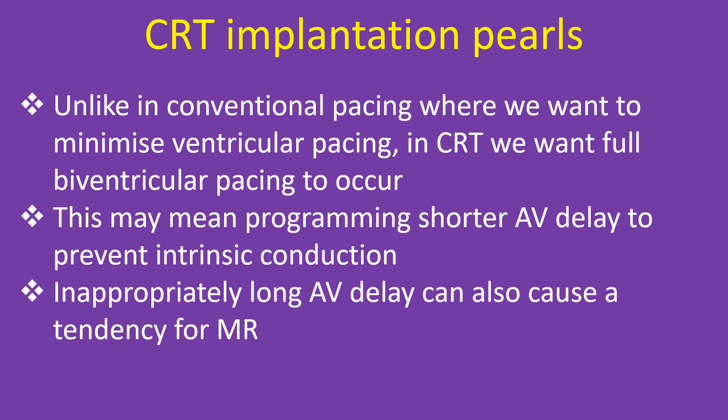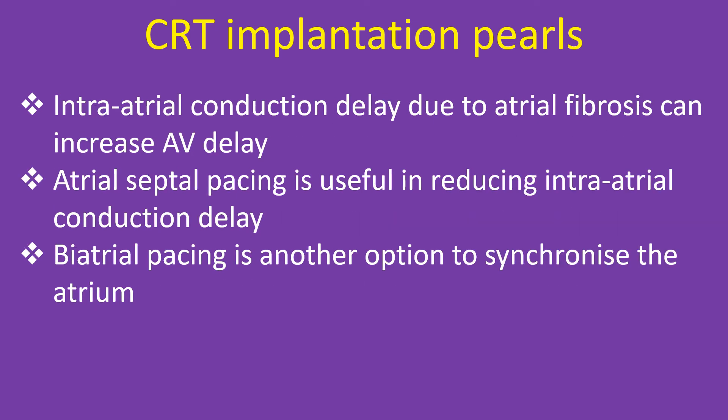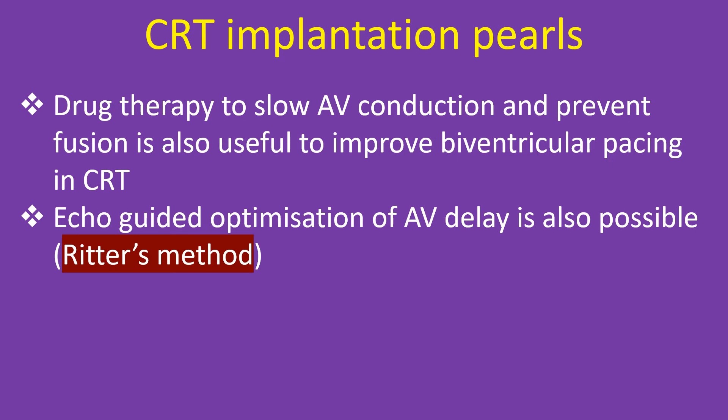Unlike in conventional pacing where we want to minimize ventricular pacing, in CRT we want full biventricular pacing to occur. This may mean programming a shorter AV delay to prevent intrinsic conduction. Inappropriately long AV delay can also cause a tendency for mitral regurgitation. Intra-atrial conduction delay due to atrial fibrosis can increase AV delay. Atrial septal pacing is useful in reducing intra-atrial conduction delay. Bi-atrial pacing is another option to synchronize the atrium. Drug therapy to slow AV conduction and prevent fusion stimulation is also useful to improve biventricular pacing in CRT. Echo-guided optimization of AV delay is also possible using Ritter's method.